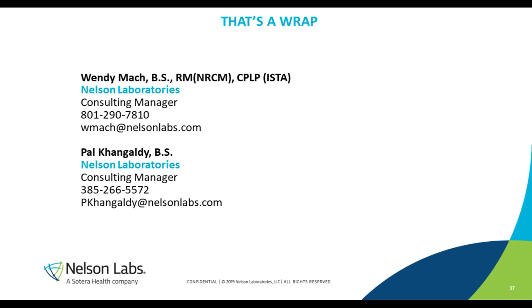Okay, let me apologize in advance if I mispronounce this word, but shall an accelerated aging test be performed under Arrhenius equations, or are there any other ways to perform accelerated aging? So the ASTM F1980, which is the recommended standard and the FDA consensus standard, does follow the Arrhenius equation. Again, if there are other options, you can use them. I would definitely suggest that you run the information by a reviewer, maybe like a Q-sub, just to make sure that they're willing to buy off on the approach, as long as the justification's there and they're comfortable with it. But again, the easiest and approved method is just to follow ASTM F1980.